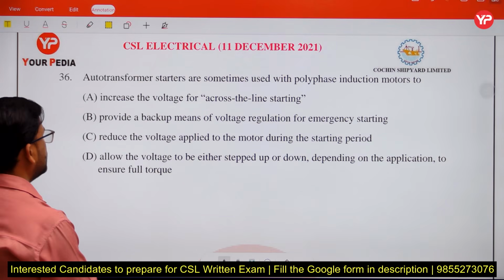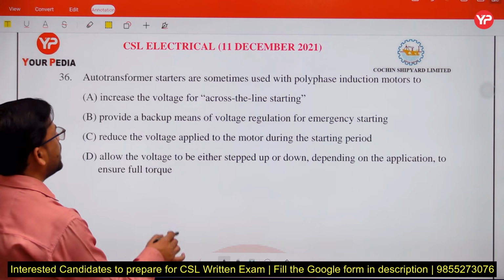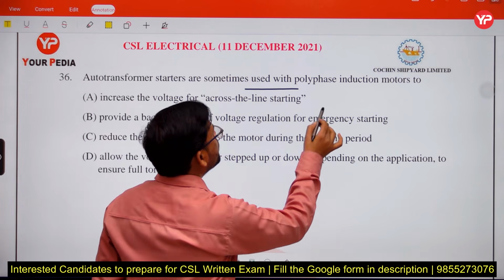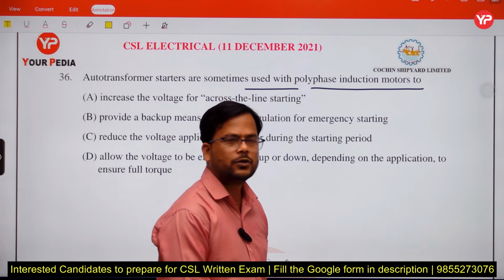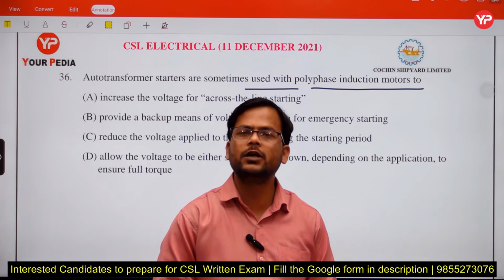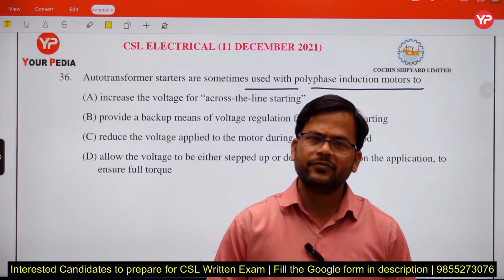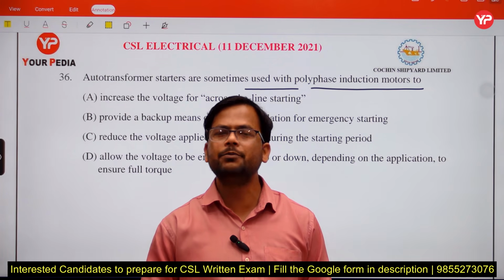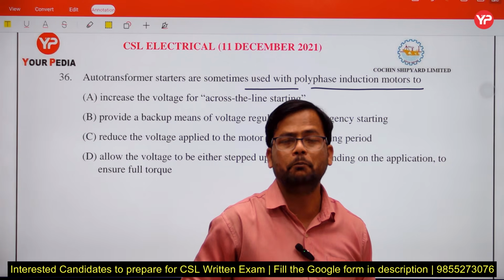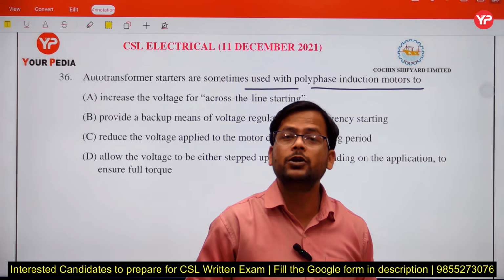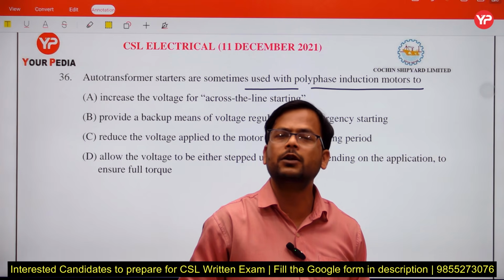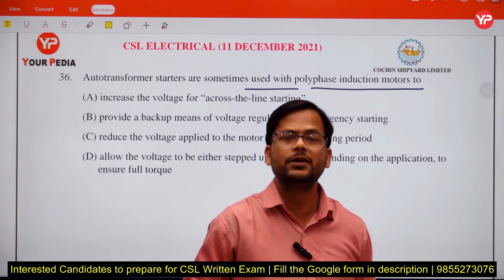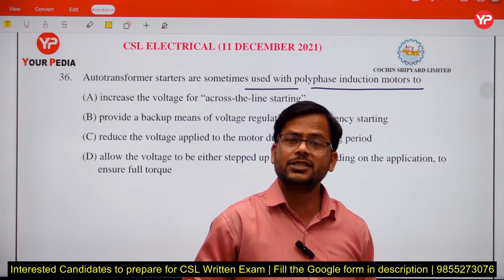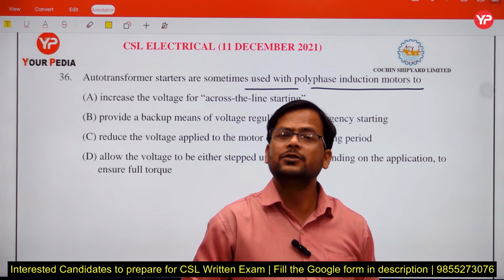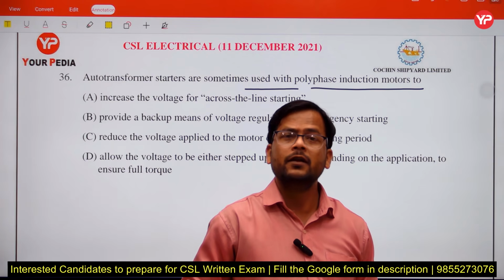Next question: auto transformer starters are sometimes used with polyphase induction motors. In polyphase induction motors, when we provide supply, current drawn from the source is 5 to 7 times the full load current, but torque developed by this current is only 1.5 to 2.5 times.